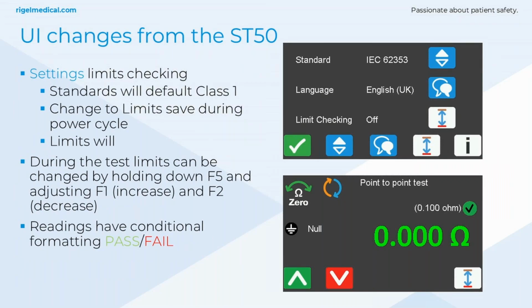So here's a little example of how it's changed and how we've introduced the settings for standards. We've introduced the limits, so it makes it easy for adjusting test limits. It's simple and it's pretty intuitive. By default, it follows class 1 standards, but you can easily customize the limits to suit your own needs. Even better than that, once you change them, they'll stay saved throughout a power cycle. So you don't have to keep re-entering the different limits every time you turn the unit on. It will be set to whatever you previously had it adjusted to.